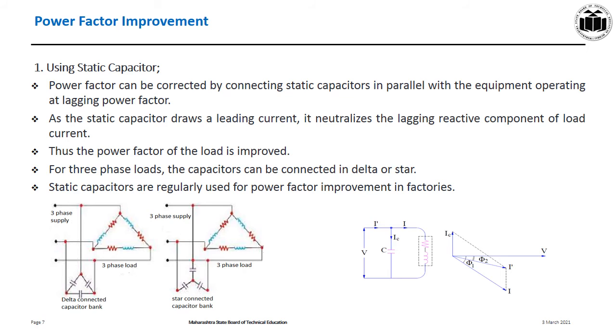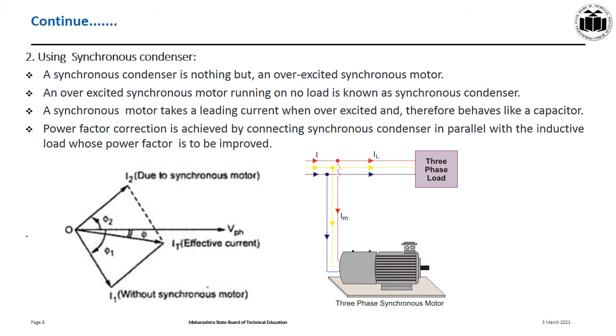Power factor improvement using synchronous condenser: A synchronous condenser is nothing but an over-excited synchronous motor. An over-excited synchronous motor running on no load is known as a synchronous condenser. A synchronous motor takes a leading current when over-excited and therefore behaves like a capacitor.